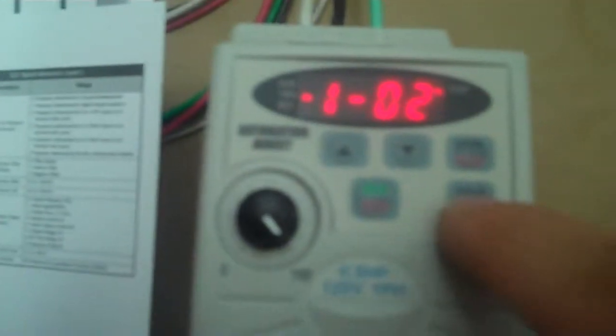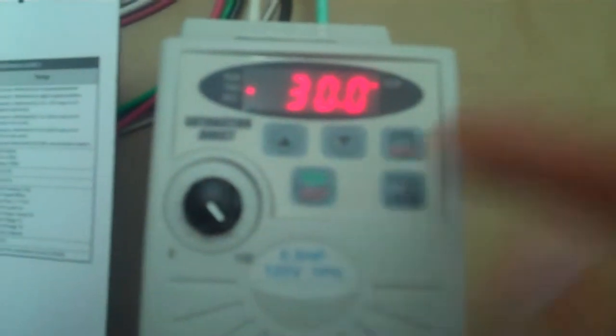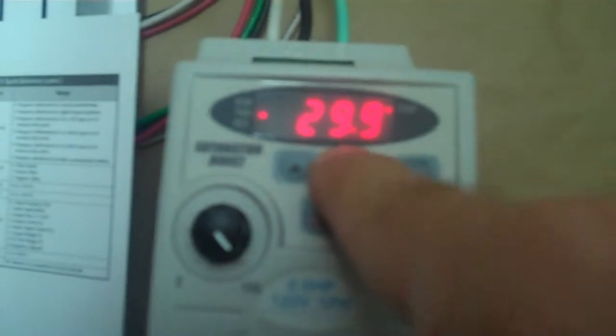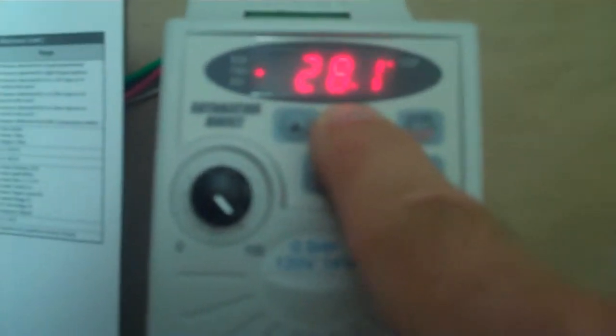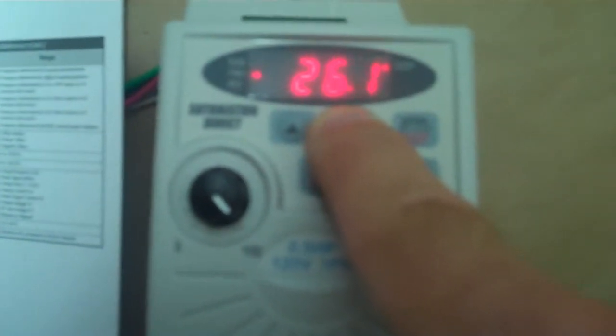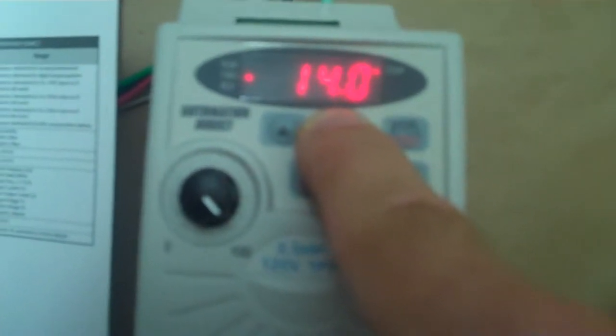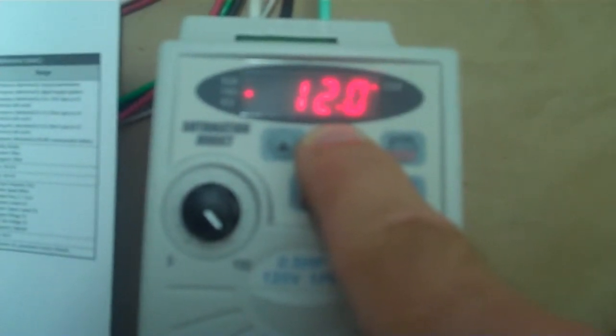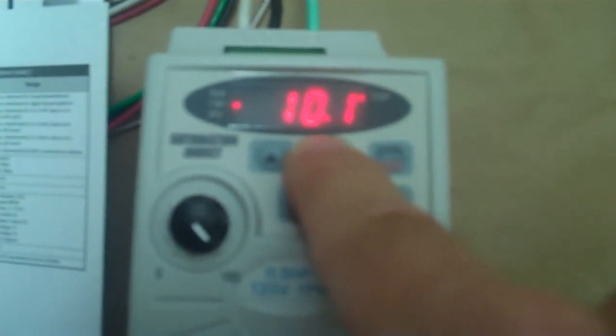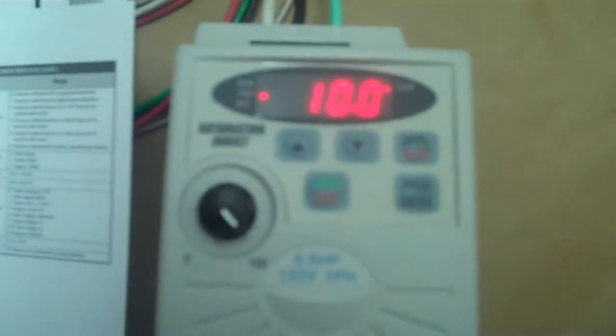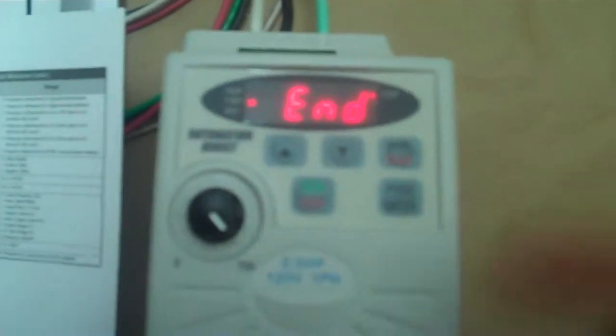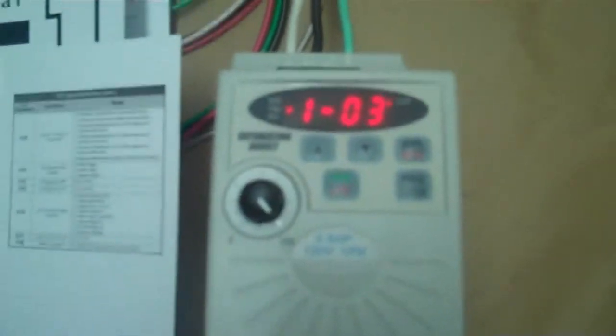And then the deceleration time. Check that it's set to thirty seconds. Now I played with this a little bit and thirty seconds seems to be a long time so we're going to use the controller to actually do a DC brake and we're going to bring that down to ten seconds. You don't have to do these steps but we've got the controller so we may as well use it. If you go below ten seconds you'll get an overload on the controller somewhere around five seconds or so. It just fritzes out and doesn't do anything good for you.